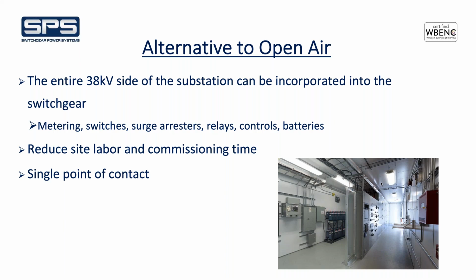So in many markets, when you talk about going out to places like California and other places, finding enough labor for the site can be an issue, and it can also be very expensive for contractors to have labor in those areas to do on-site work. So by utilizing switchgear, many times you can significantly reduce the site labor and also the commissioning time on site because the switchgear and all the components are integrated at the factory. It can be tested thoroughly prior to shipment.